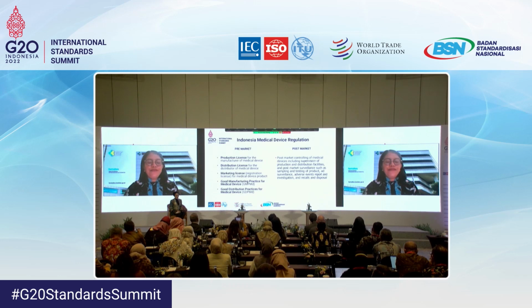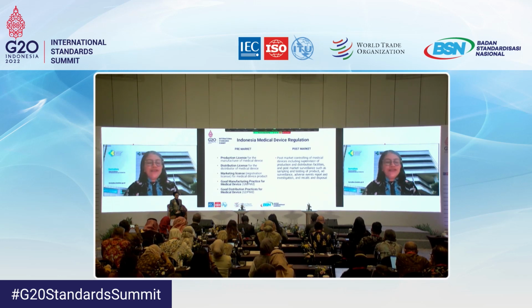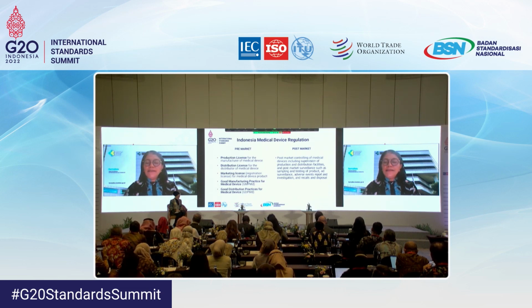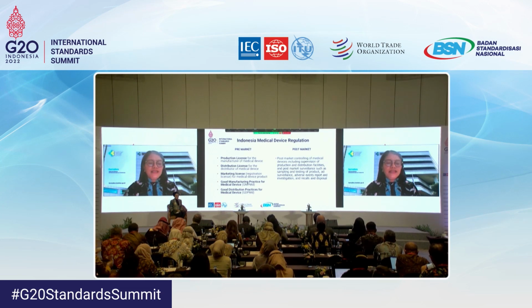The controlling of medical device in Indonesia is done to ensure that the device is safety, quality, and have good performance when it is used by the user, and the final aim to ensure the patient safety. The controlling of medical device is conducted in pre-market before the device distributed, and in the post-market when the device is in the market according to the life cycle of the medical device. It means that the quality and safety must be ensured from the device is manufactured by manufacturer, then distributed by the distributor until the device has achieved its lifespan and need to be disposed.